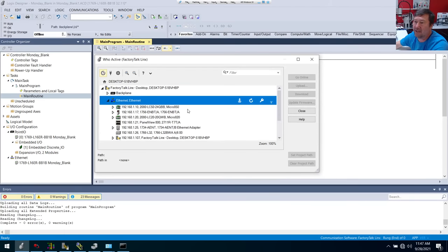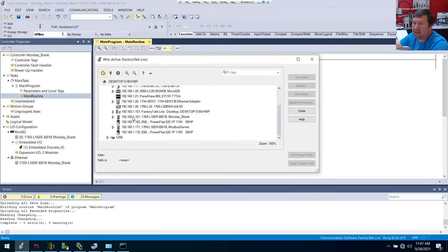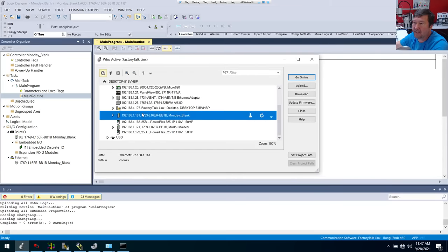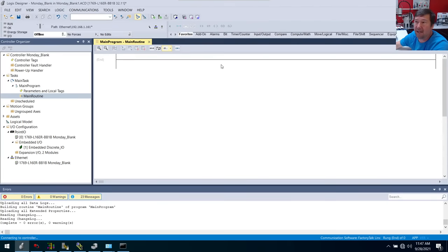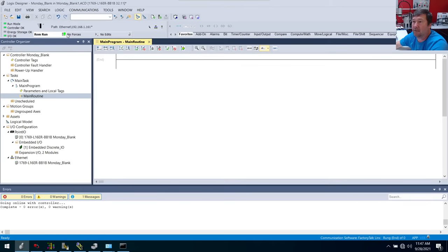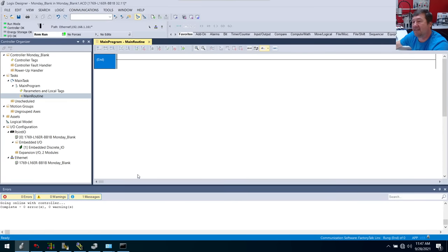Now we see the same error as before but now we look here and we're not browsing our PLC. So I can go to Ethernet, and now I can go to 192.168.1.161 because that is our Monday blank one. And then if we feel this is the offline program, I should be able to just go online, even though it's a different path. And it looks like it's going online. And there you go — now we're online. This is by far the easier way to go online with Ethernet.